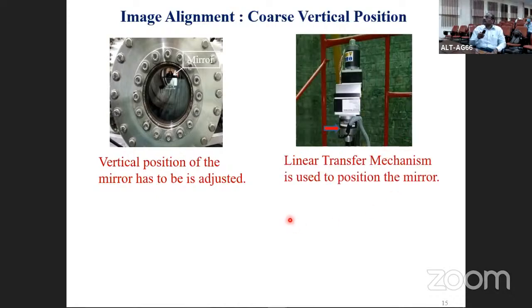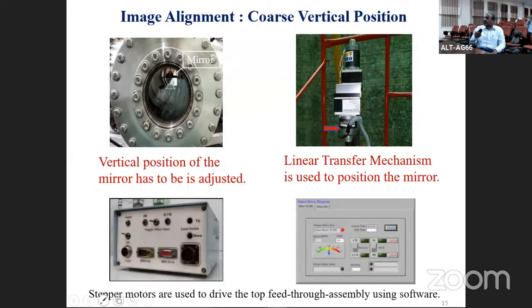This is achieved by using the linear transfer mechanism of the top header assembly. You see a stepper motor here, and there is a gear down box, and on the other side there is a bellow which opens up or contracts. It has a certain limited range, and we use a stepper motor controller, which is home built, and a software which is developed for our application to accomplish this job. Here we can select which motor you want to use, what speed, which direction, which mode, everything, which is software programmable, and one can make use of this visibly by seeing at the mirror.